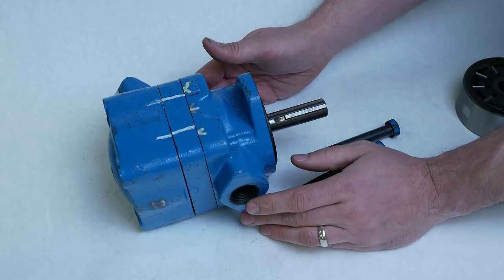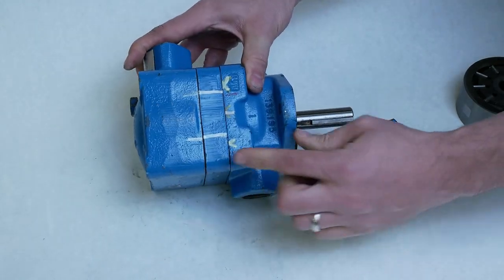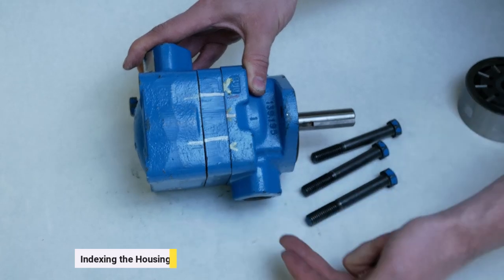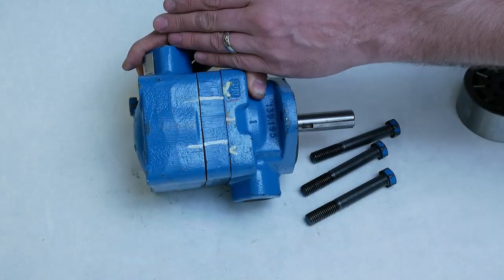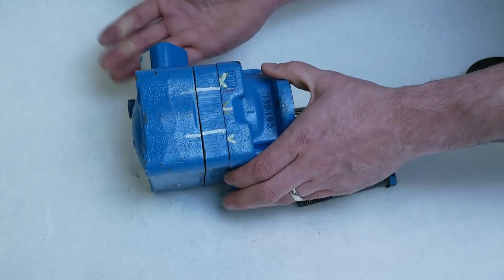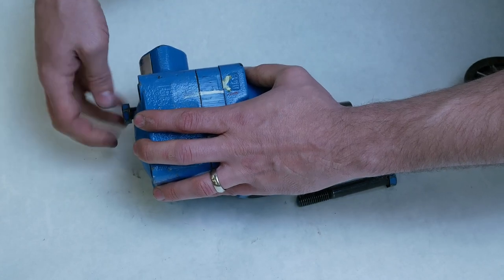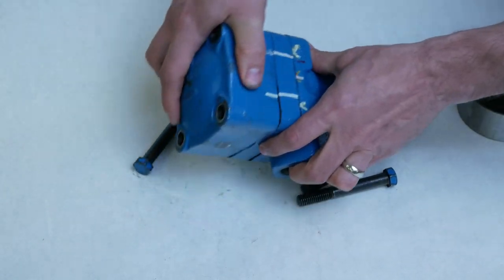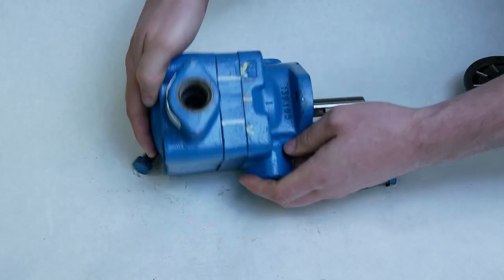So as we talk about the vane motor being indexable this is what we're talking about. We can actually reassemble the unit properly and use it with the A and the B port instead of lined up on the same plane they can actually be 180 degrees from each other. They would actually be able to be indexed 90 degrees by simply changing pulling the hardware out and rotating the end housing just like that.